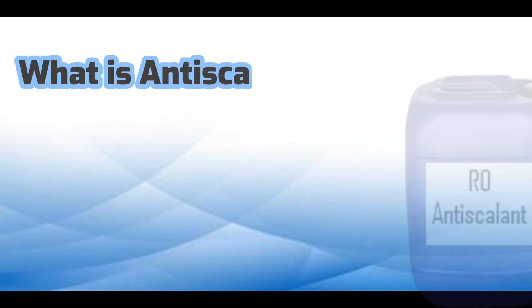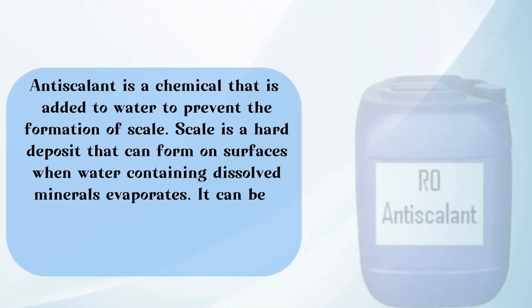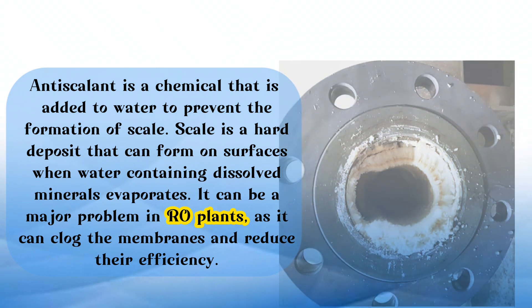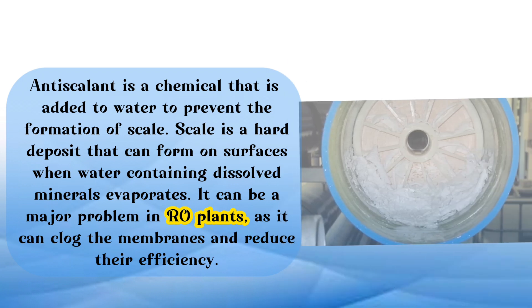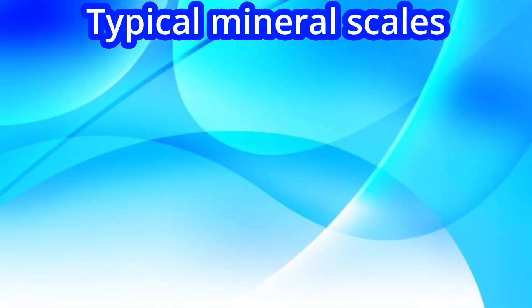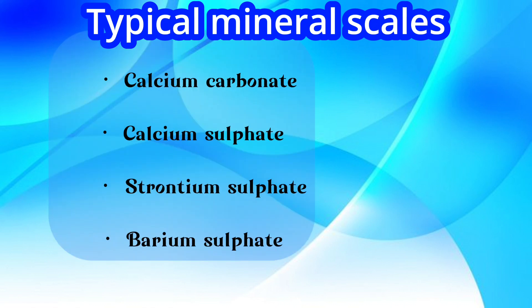Antiscalant is a chemical that is added to water to prevent the formation of scale. Scale is a hard deposit that can form on surfaces when water containing dissolved minerals evaporates. It can be a major problem in RO plants, as it can clog the membranes and reduce their efficiency. The most typical mineral scales to be concerned about are calcium carbonate, calcium sulfate, strontium sulfate, and barium sulfate.